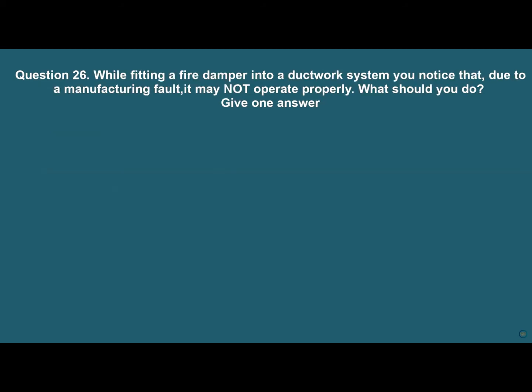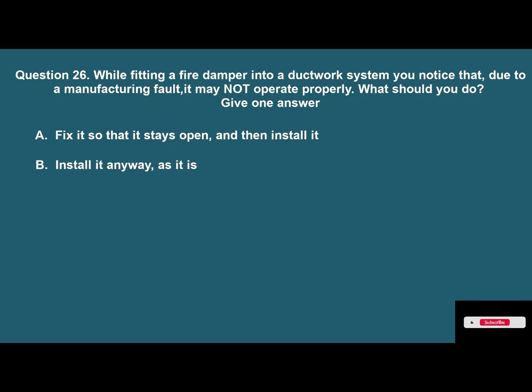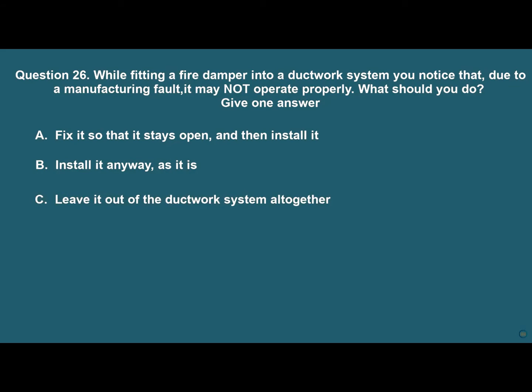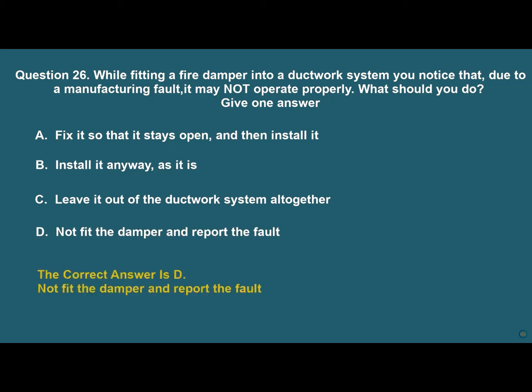Question 26: While fitting a fire damper into a ductwork system, you notice that, due to a manufacturing fault, it may not operate properly. What should you do? Give one answer. A. Fix it so that it stays open, and then install it. B. Install it anyway, as it is. C. Leave it out of the ductwork system altogether. D. Not fit the damper and report the fault. The correct answer is D: Not fit the damper and report the fault.